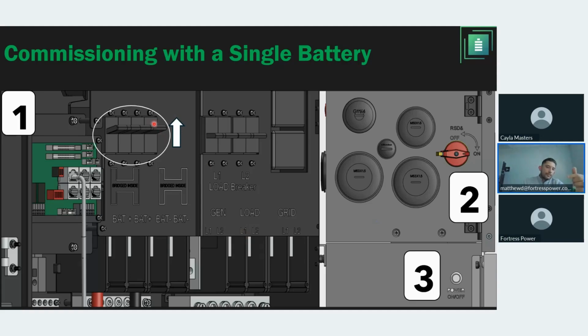So flip the DC breaker up and then turn the rapid shutdown switch to the on position, right? Doesn't mean that you're initiating rapid shutdown. This means rapid shutdown is off. So if you wanted to actually do rapid shutdown, you would turn it to the left position. So turning the battery on, flip it to the right, and then energize with the power button on the bottom.